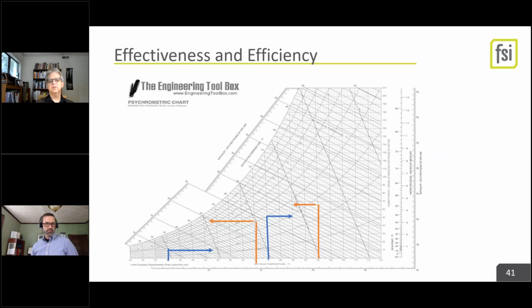Oh no, it's a psych chart. You guys all remember psych charts, right? So we want to talk about effectiveness and efficiency. We have some manufacturers of heat recovery cores, and that can be the core that only does heat recovery, or energy recovery cores that do latent and sensible, that want to give us efficiency. And that's really a theoretical maximum for that surface area and how much they actually gain. And that has nothing to do with what actually happens or what we care about.